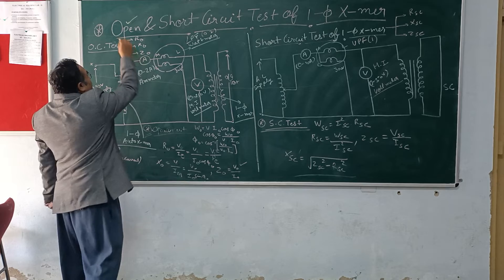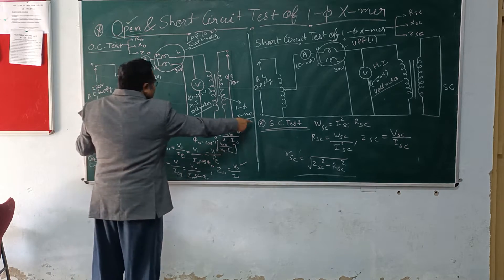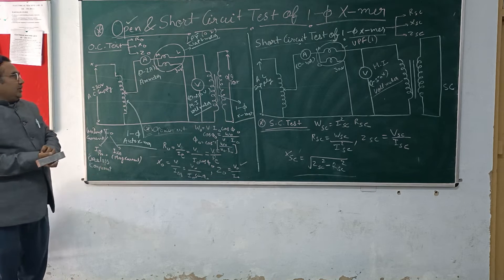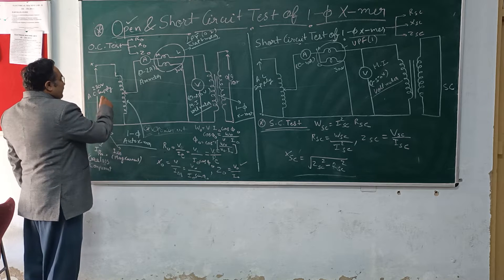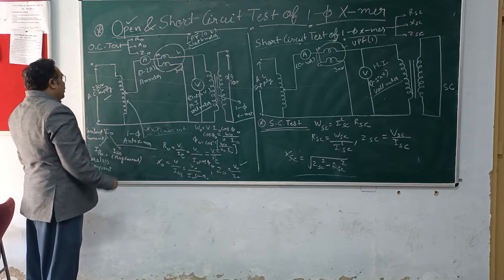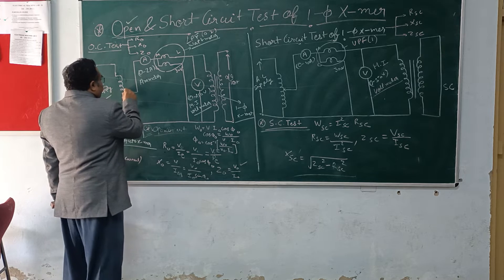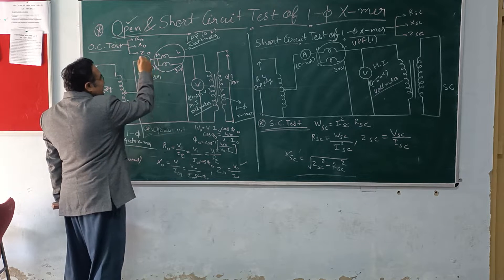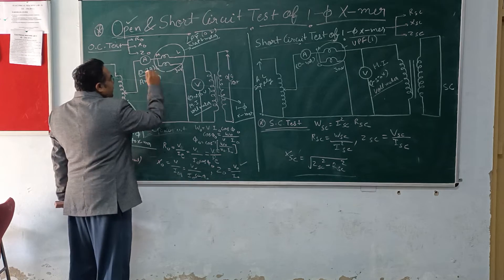Let us first focus on the open circuit test. You can see this is the schematic diagram of the open circuit test on a transformer. What we have in this circuit diagram: we have an autotransformer which can provide a variable AC supply up to 240V. Then one of its ends is connected to an ammeter - this is an AC ammeter, a moving iron type ammeter of range 0 to 2 amperes.